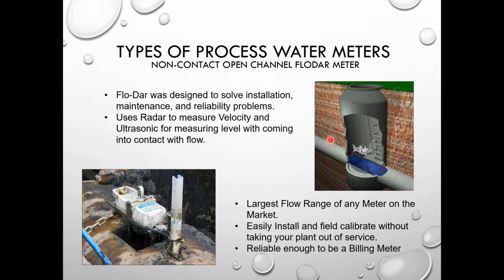Non-contact flow meters. So non-contact flow meters were designed basically with maintenance in mind. So they wanted to have a meter that would stay out of the flow, right? So this flow meter here uses radar for velocity and ultrasonic for depth. It's a very large flow range for this flow meter. We're talking upwards of a 120-inch diameter pipe all the way down to 4-inch. And they're easy enough to install and maintain.